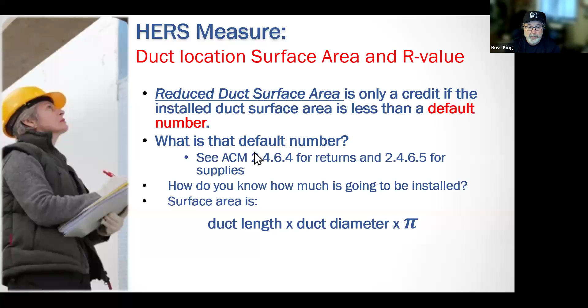Verified low leakage ducts in conditioned space. So if you claim ducts inside conditioned space, let's say they're going to drop a soffit in the hallway and run the ducts through that, that's inside conditioned space. It still needs to be duct tested. Okay. And it's a leakage to outside test. So a leakage to outside test is where you're pressurizing the ducts and you're pressurizing the house at the same time. So if the house is pressurized and the ducts are pressurized, the only leakage that can happen is from the ducts to the outside of the house, because the house is pressurized to the same pressure as the ducts. So that's a pretty involved test.